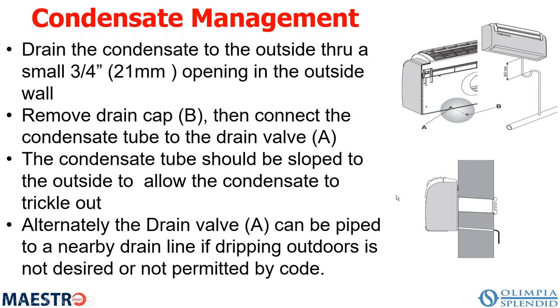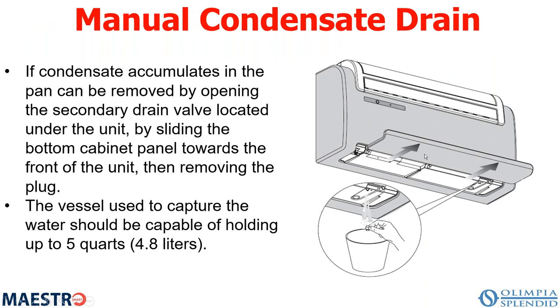In the summertime, it's not a problem. It all gets evaporated, or most of it gets evaporated. But in the wintertime, if enough condensate builds up, the second float turns off the unit. The second float is a normally closed switch. So when the water rises to that level, it opens and shuts the unit off and gives you a code saying block drain. At that point, all the consumer has to do is open up a door on the bottom, pull out the plug, and just drain the water out. And then put the plug back in and turn the unit on, and you're back in business.